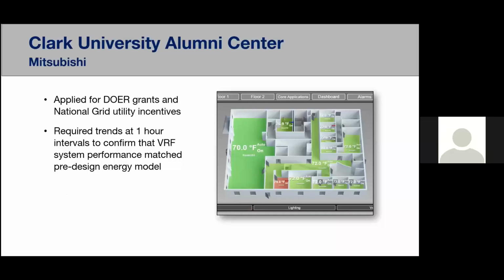So this is one of these projects that applied for DOER grants and National Grid utility incentives. We ended up getting around, I believe, $50,000 to $100,000 for this project for energy savings. But one of the things that needed to be done through controls was trend hour intervals to confirm the VRF system matched exactly what the pre-design energy model was, to match exactly how it was operating. We did that throughout the course of a couple months, and we decided that the grants would pass, and it went through. So a pretty cool project, able to use simultaneous operation to our advantage, with flexibility along with it, and provide low ambient heating capabilities without any backup heat whatsoever. So yeah, this would be Clark University Alumni Center.